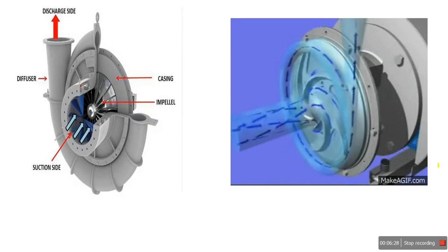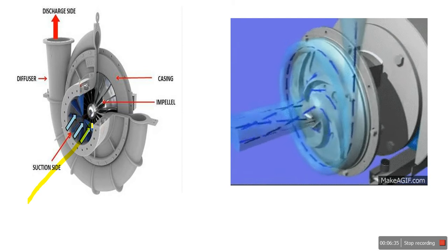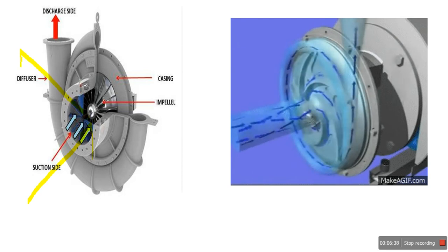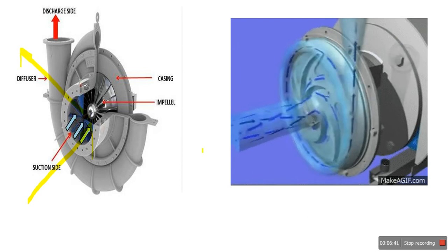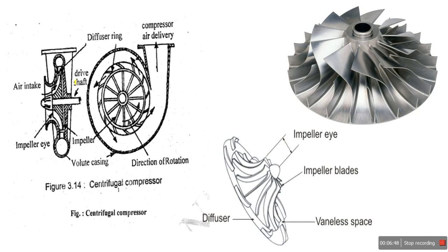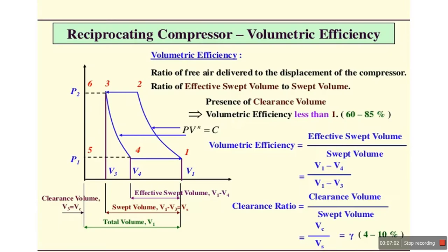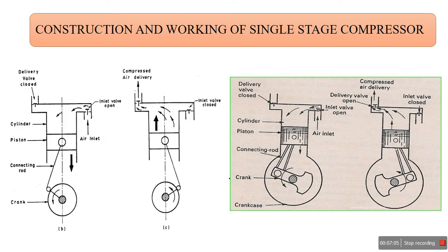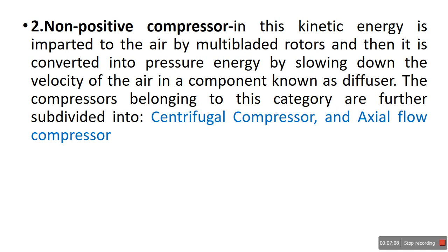Now we move to the centrifugal compressor. This is a type of compressor where air enters axially and moves outward radially. The air enters and passes through the impeller, and at the end of the impeller the periphery interfaces with the diffuser ring, which plays a very important role. It works on the dynamic principle — this is a non-positive displacement compressor where kinetic energy is imparted to the air by multi-bladed rotors such as an impeller.